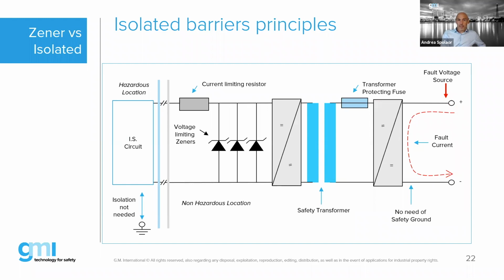The difference with the isolated barriers is that the field sensor doesn't need any isolation from ground, and the barrier, the isolator, doesn't need any connection with ground. The 1 ohm needed in a Zener application is not needed for isolators. In this case, the voltage source will be led directly to ground without interfering, because here there is a safety transformer. There is isolation between the safe area and the hazardous area.